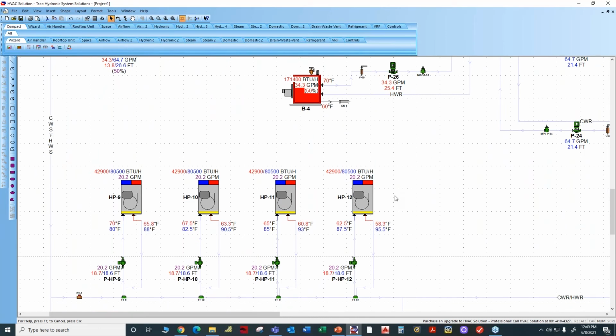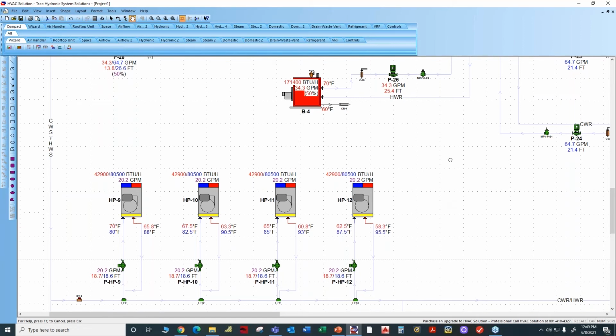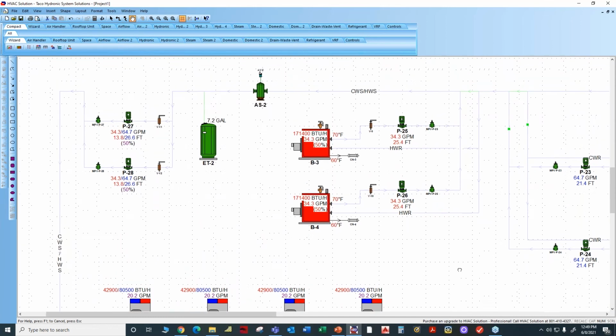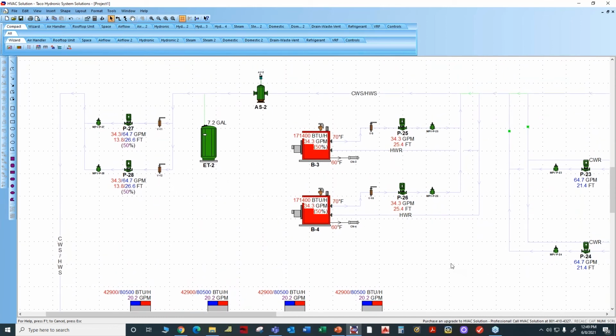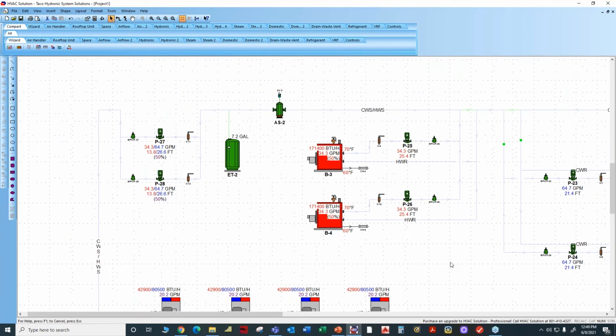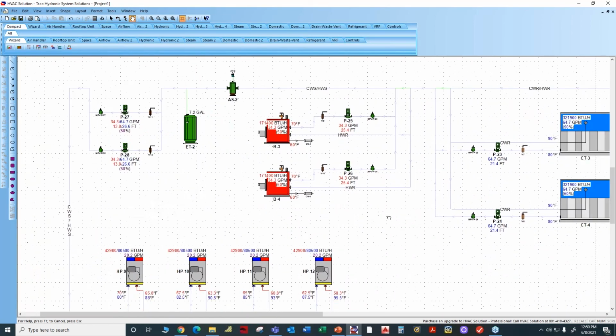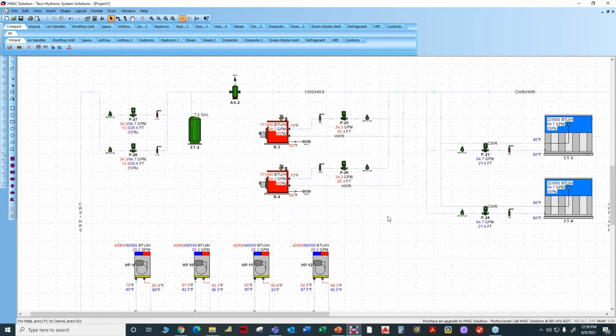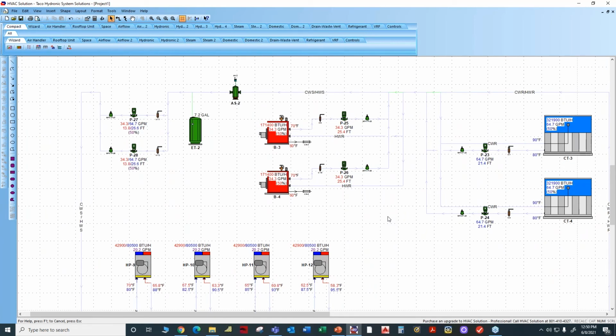Yeah, especially like you said, in the center section of the country and also in the south. And then we tend to see fossil fuel, usually natural gas is the most popular, but not exclusively. In the north, north of the Mason-Dixon line and north of the border, you definitely want a backup boiler on a heat pump system. Yeah, for sure, because there will be times when probably every heat pump is calling for heating, and you need that backup at that point. Wouldn't you agree with that, Rich?